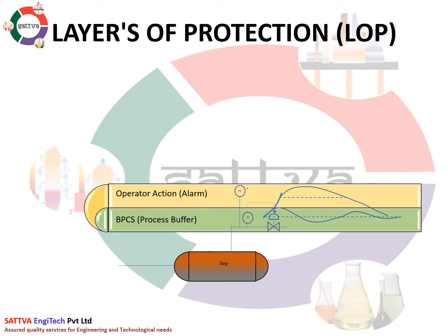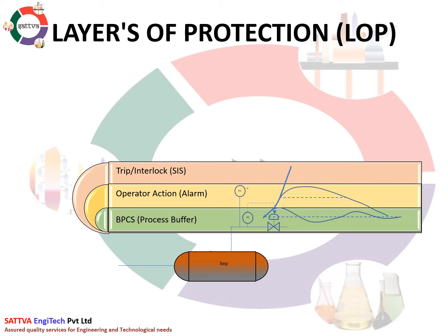If this layer fails, then the third layer of protection comes into picture — either trips or interlocks — wherein the safeguarding system overrides and closes or trips the system so that it will not escalate further. Usually the system is kept separate from the control system, and this causes stoppage of production such as stopping inlet shutdown valve or tripping the pump.